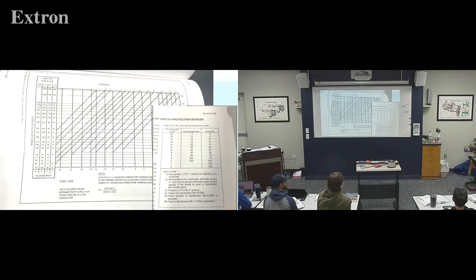They do make time delay fuses that incorporate some funky stuff into them, and a time delay fuse gets closer to the circuit breaker as far as how it works, but then we'd start splitting hairs, and the FAA isn't going to give us a whole other set of charts. So the answer is just the way they trip. They'll let you run a little more power through a circuit breaker because it has, I'll use the word, a time delay cooling effect, the same as your wire does.